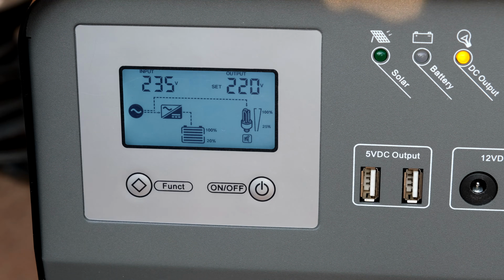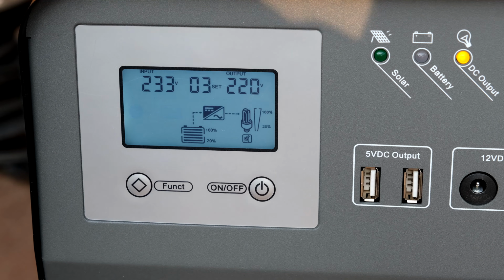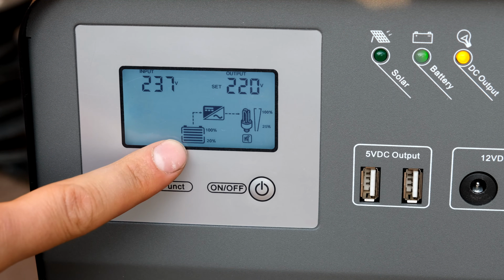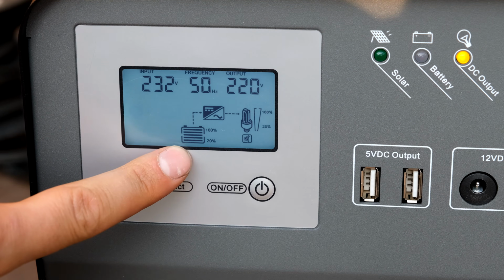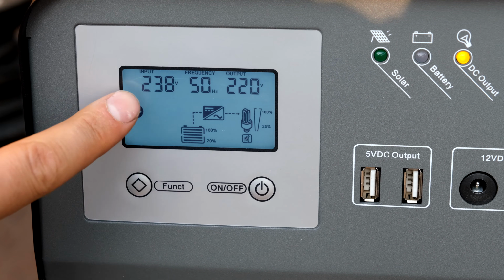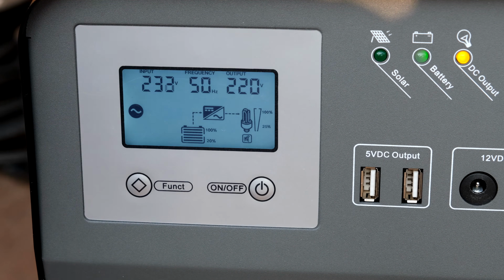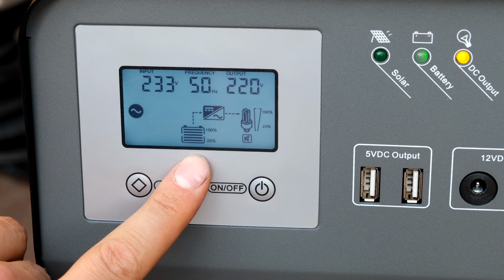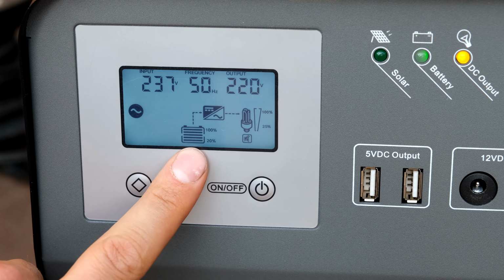So if I leave it on the 3 mode, it's called the battery priority mode. Notice that it immediately switched to the battery even though the supply has a stable input. Now this is useful for 2 reasons. The first one is you can use your external supply. The second one is if you've got an unstable input voltage, for example if it's a generator, you can force the unit to feed the load via the battery.